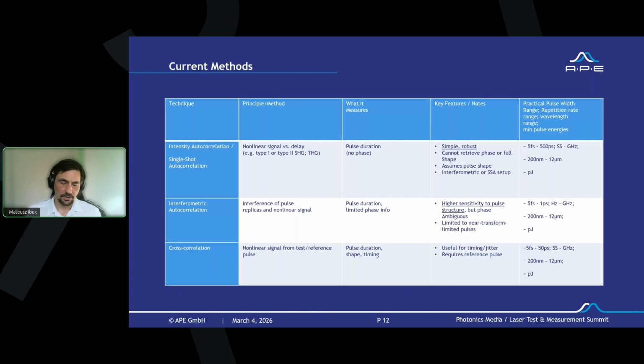And the third correlation method is the cross correlation, where we combine two different laser beams with different wavelengths and different properties. So we use the nonlinear signal from a test and a reference pulse. It gives us only the pulse duration in certain combinations. When one very short pulse is combined with a long pulse, it can give us the shape and the timing of the two pulses relative to each other. So this is useful for timing or jitter measurements. It requires two laser pulses, so it requires a reference pulse. And the specifications are almost the same as for autocorrelation.